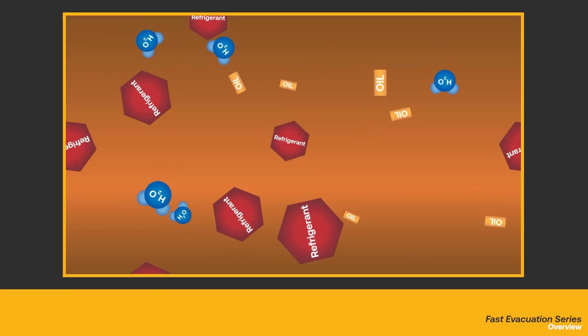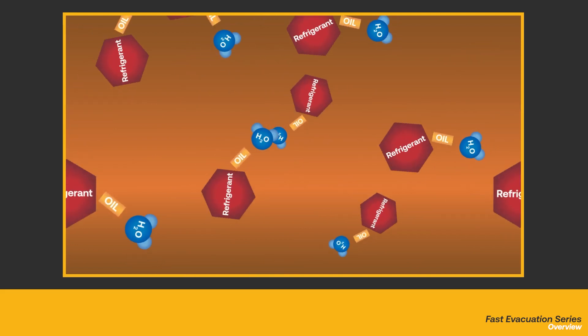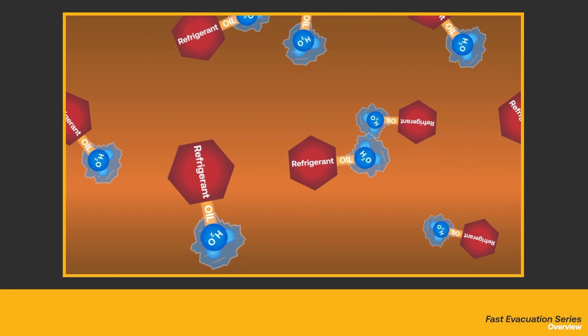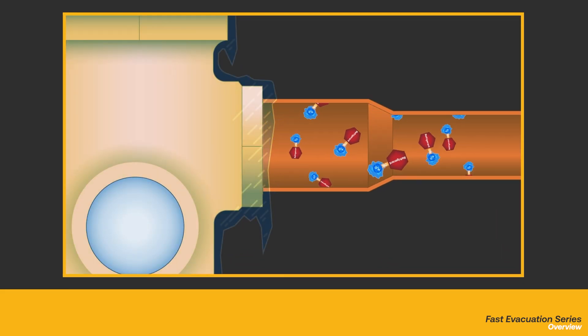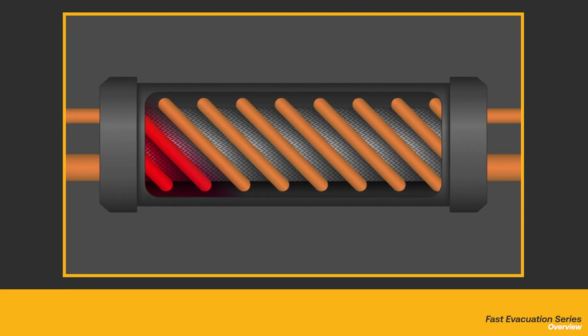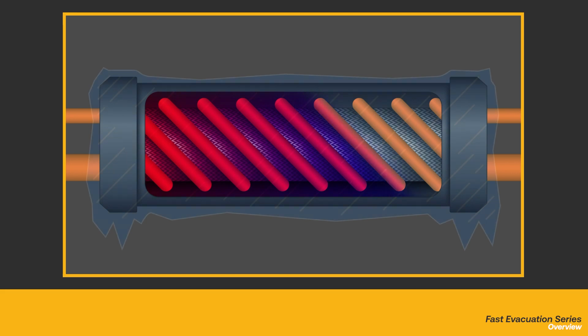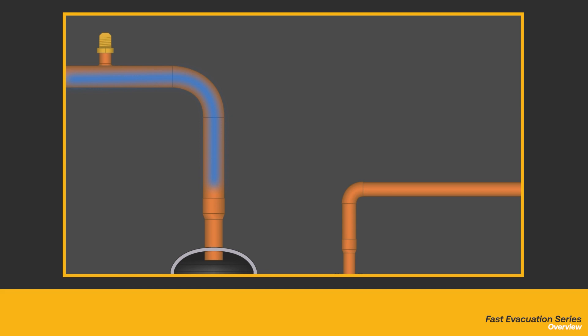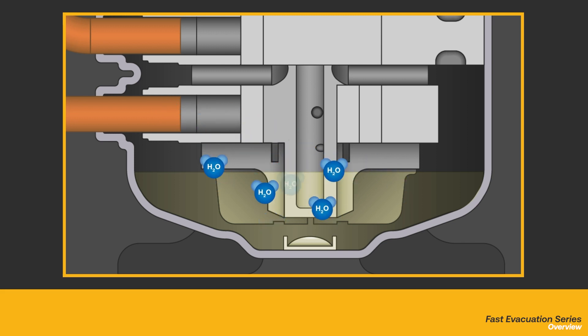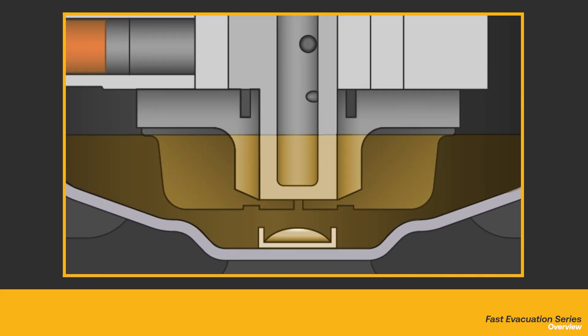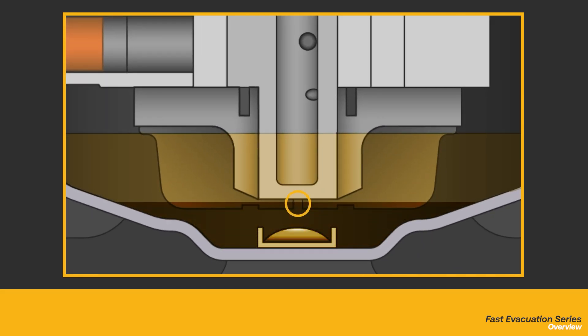Both refrigerant and compressor oil are hygroscopic, meaning moisture is absorbed quickly. As refrigerant circulates through the system, the moisture will freeze in components such as the expansion valve, causing blockages. It will also reduce the heat exchanger's capacity to absorb and reject heat, reducing system efficiency. As the refrigerant enters the compressor, it carries moisture which mixes with the compressor oil. This will negatively affect the oil, altering its viscosity and lubrication capabilities. This turns the oil into a sludge that can build up and block strainers, valves, capillary tubes and other components.